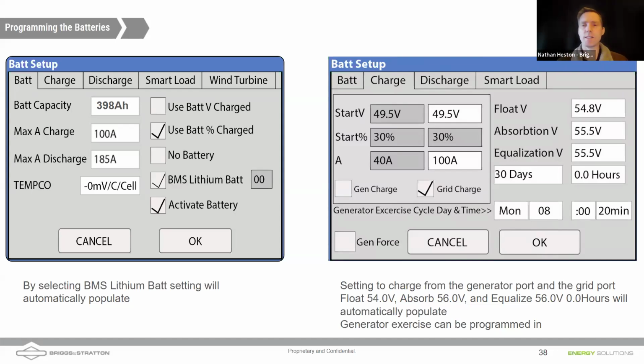Now, best practice here, Daniel, would actually be to go through without the BMS lithium battery box and without the communications checked. And that's actually, put in the values for float, absorb, equalization, just in case you ever have an instance where you lose communications. You want to have those, the inverter will default to the manually programmed set points, and we can put those voltages in. What is float and absorb for our batteries, Daniel?